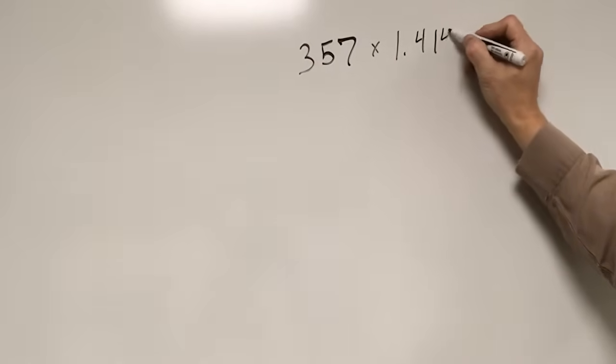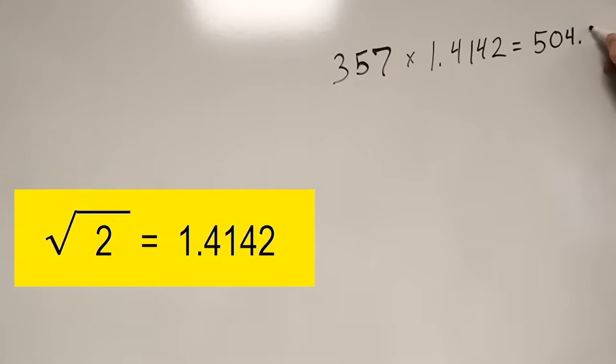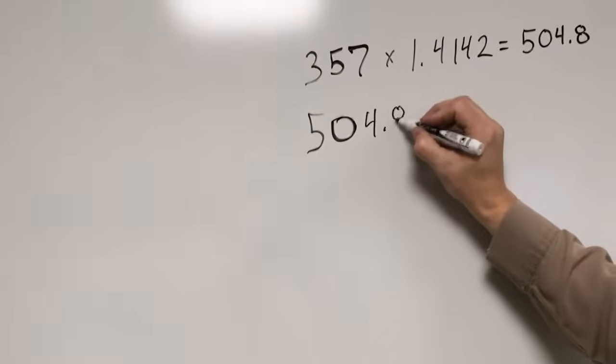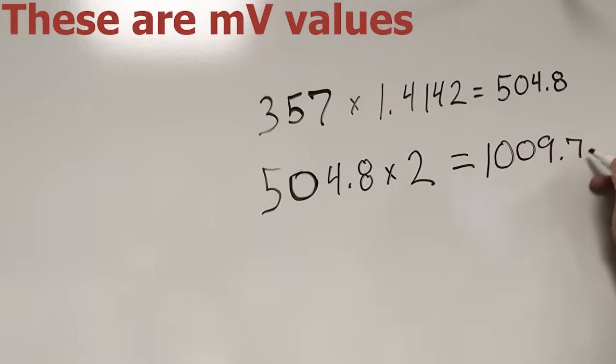Begin by multiplying the value displayed on the screen by the square root of 2, then double that number. This is the amount of actual voltage fluctuation produced by the proximity measurement.